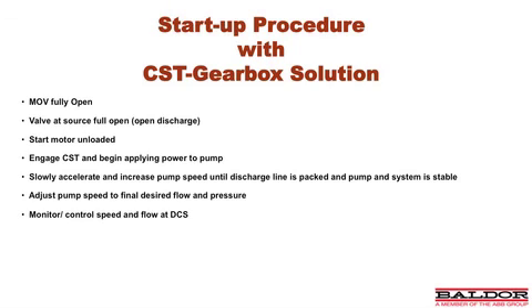That being said, as we go through the process, the valve at the discharge of the condenser would be fully open. So now you're starting the motor. The motor is started unloaded. It gets up to speed, at which time you start engaging the CST. Now, you may have your MOV start to open at that point, or it may already be open depending on your particular application. At any rate, the CST begins to apply power to the pump. Now the pump is starting to turn. The unit slowly accelerates. You increase pump speed until the discharge line is packed and stable, at which time you adjust the pump speed to the final desired flow and pressure, and then you monitor the control speed and flow at the DCS. It's that simple.